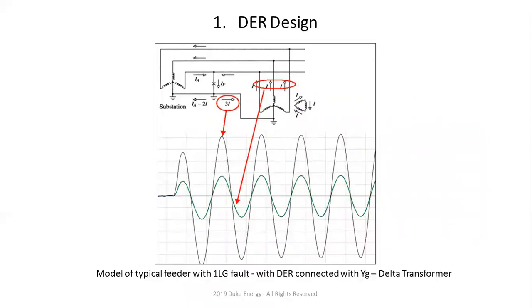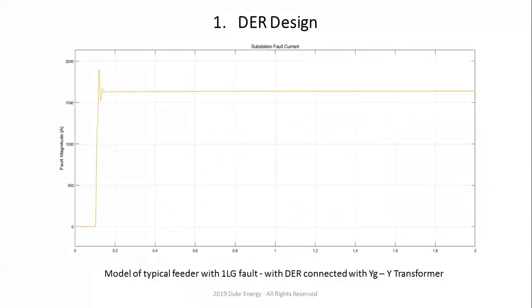And I have run the analysis, and that says for about 2 megawatt size of PV on this particular feeder that I simulated, which is a generic feeder, we would not be able to see that without typical settings. So our typical settings are 900 for phase and typical 600 for ground, right? So from that standpoint, you can clearly see that there's no reason to put a Y grounded delta transformer unless something else is done to the protection and control settings, right? So what do you do now?